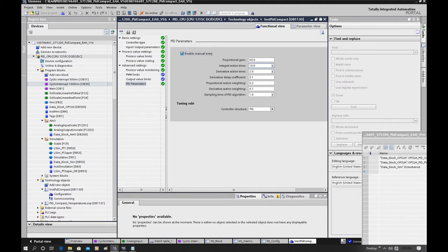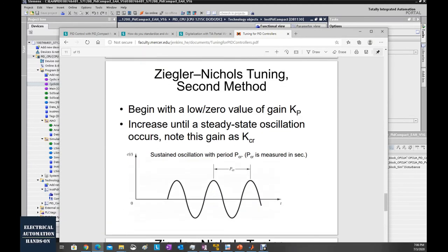To implement the Ziegler-Nichols method — recalling the second method — firstly we need to give a small gain value and gradually increase this gain until the system gets this oscillation. At that moment, we need to record the KCR and the PCR value. Let me shift to my system and go to the HMI.